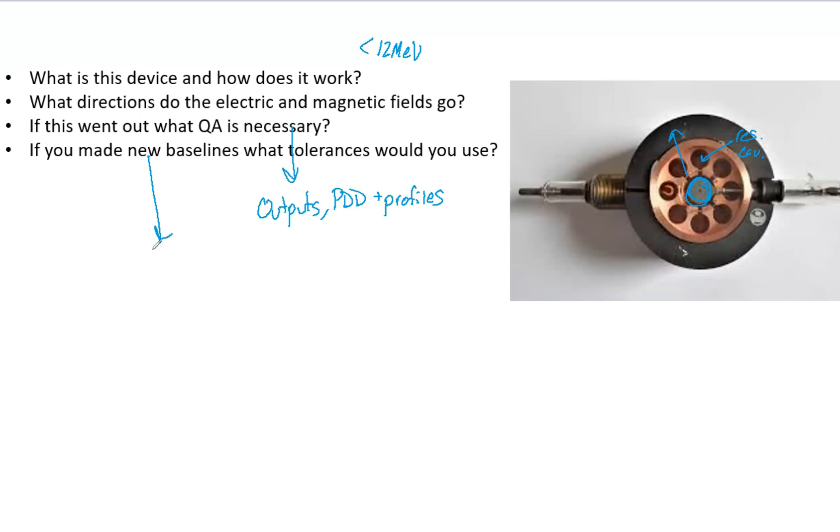Now if you had to make new baselines, what references and tolerances would you use? First thing I would want to use is TG-142 as a reference, and I would want to use the annual tolerances. Remember what we're trying to do ultimately is make our machine replicate what we have in our treatment planning system.